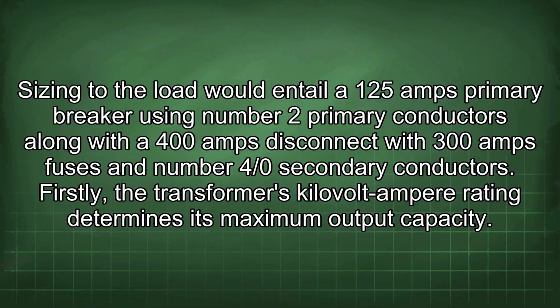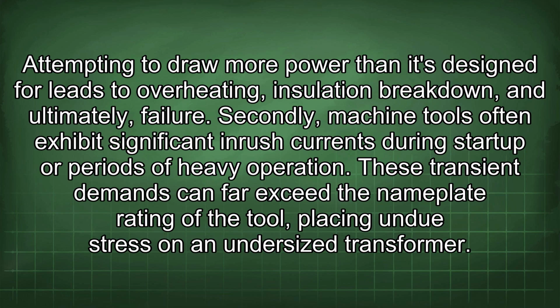Firstly, the transformer's kilovolt-ampere rating determines its maximum output capacity. Attempting to draw more power than it's designed for leads to overheating, insulation breakdown, and ultimately failure. Secondly, machine tools often exhibit significant inrush currents during startup or periods of heavy operation. These transient demands can far exceed the nameplate rating of the tool, placing undue stress on an undersized transformer.